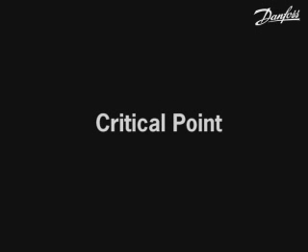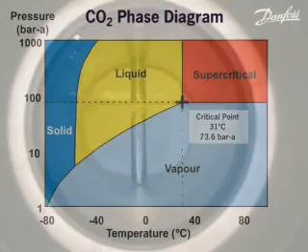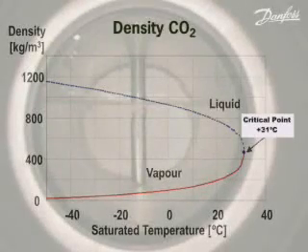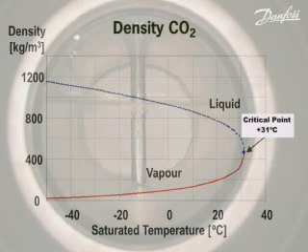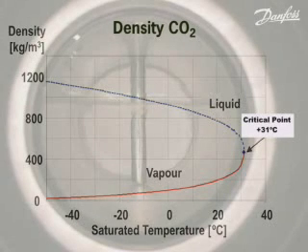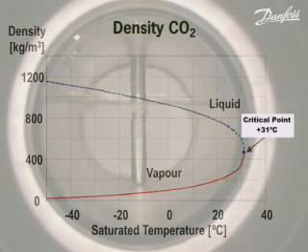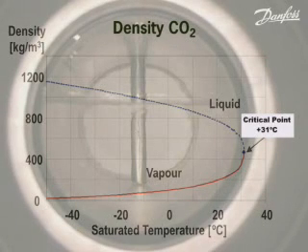We would now like to define the supercritical phase. In the next sequence, the CO2 will be heated to increase its temperature and pressure to the stage where it passes through its critical point into the supercritical phase. The critical point is the pressure and temperature combination at which the density of both the liquid and vapour are equal. The distinction between the liquid and vapour phases disappears gradually as the pressure and temperature increases towards the critical point, until only a single phase exists in the supercritical area. The density of CO2 at the critical point is 468 kg per metre cubed, which is of the same order as many liquids, but is nearly 2.5 times higher than the CO2 vapour density at the starting point of 20 degrees C.